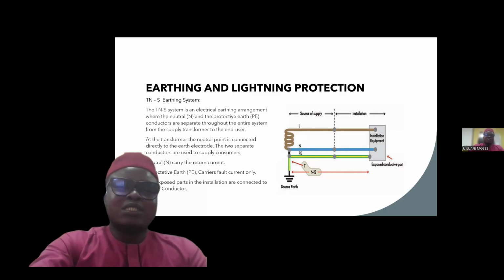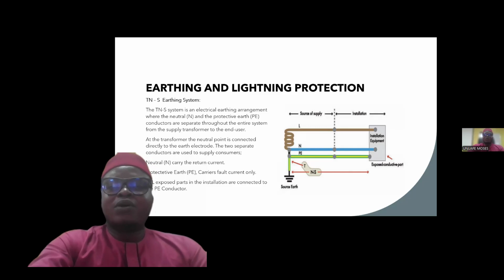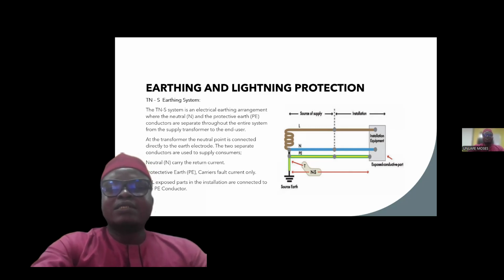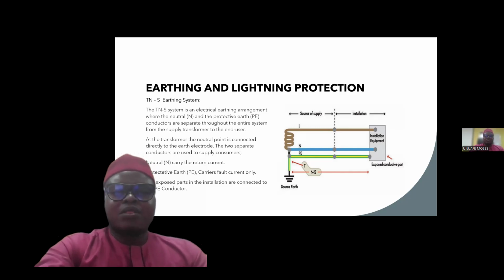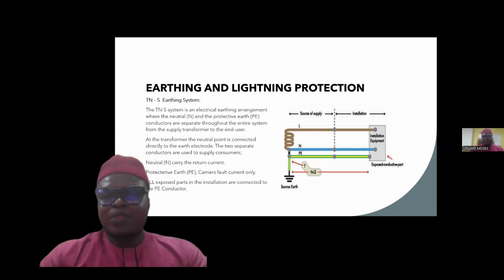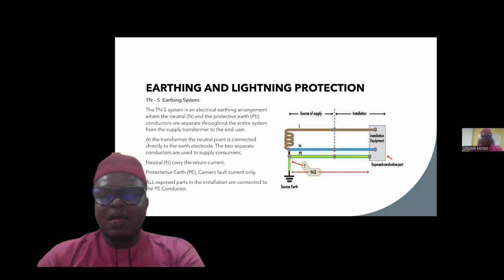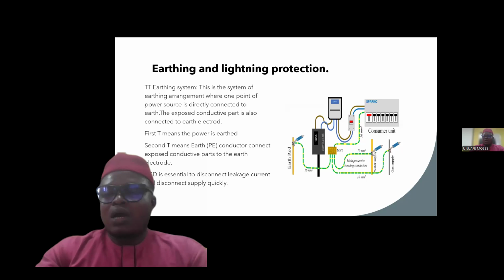Why do we have to use this TN-S? The reason for us to use this TN-S is that the underground cable armoring or lead sheath or steel wire armor provides a reliable earth path, reducing electrical noise and fault potential. Now, if you look at this system, it is also applicable to an industrial area, but basically a residential and commercial area. Now, another type of earthing system is the TT earthing system.